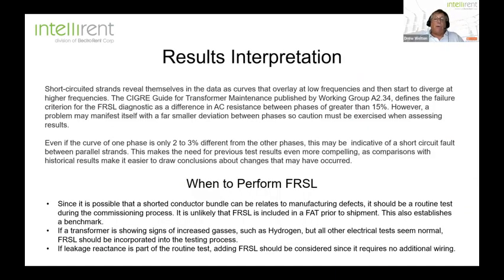Now, if I go back to this previous slide, this will give you some interpretation of when you should be concerned in terms of the deviation between the three strands. Anything greater than 15% difference in the measured resistance between the strands is probably going to indicate that you have a serious problem, or that you have this shorted conductor bundle.